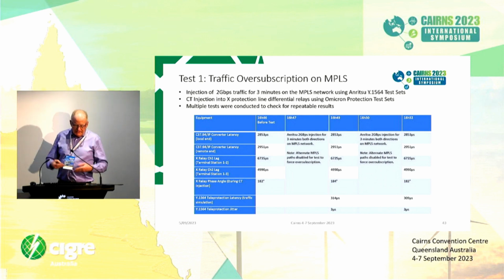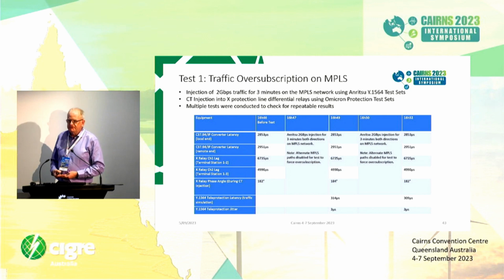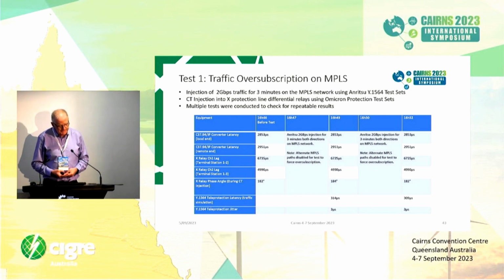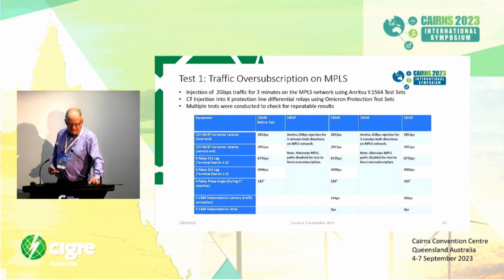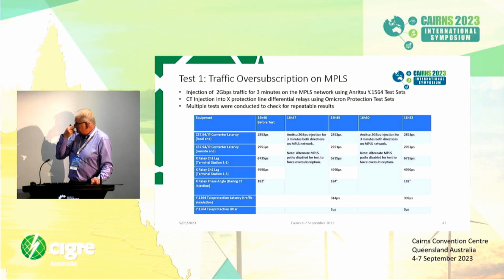Given that we've got a 1 gigabit per second backbone, obviously 2 gigabits, you're oversubscribing by a factor of 2. At the same time, we're also running, via our injection test sets, some current injections into the protection relays to simulate the line differential traffic. And we also ran multiple tests just to make sure we were confident we were getting consistent results. So this is a summary of some of the testing we did for this test.